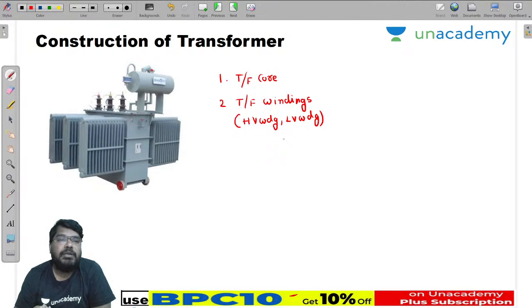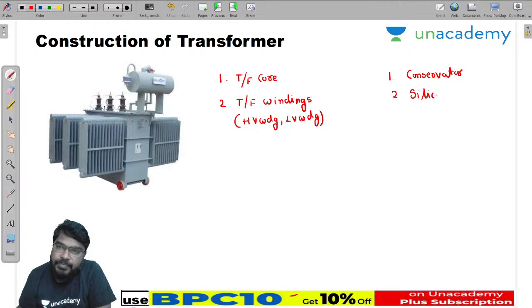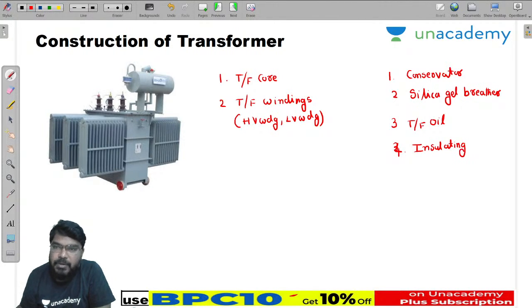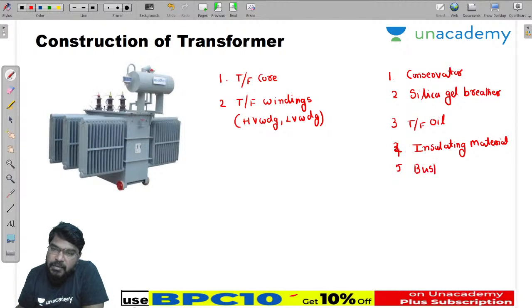In addition to these major parts, there are some minor parts. One is the conservator, second is the silica gel breather, third is the transformer oil, fourth is the insulating material used between the laminations of the transformer core and the strands of the transformer windings, and fifth is the bushings, which are the incoming and outgoing terminals. So these are the minor parts.